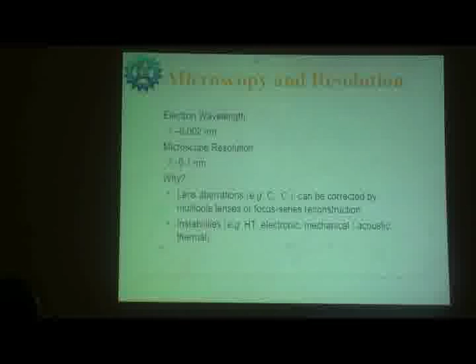With the electron wavelength, at something like 300 kV, we can go to a wavelength of about 0.002 nanometers. But the electron microscope resolution is still only about 0.1 nanometer, because a lot of factors limit the resolution to the extent of what you get from the wavelength of the electron beam. One of the factors is the aberrations, as we see in the general optical microscope, and the instability caused by electronic, mechanical, acoustic and thermal factors, many factors which limit the resolution you get from the wavelength.